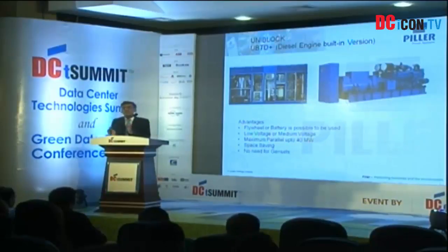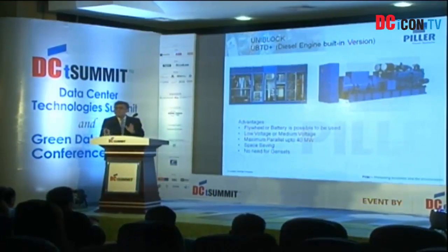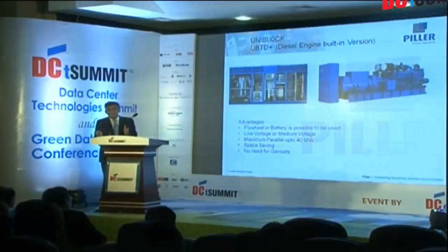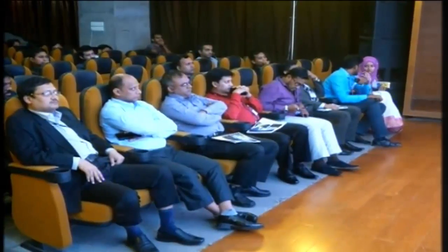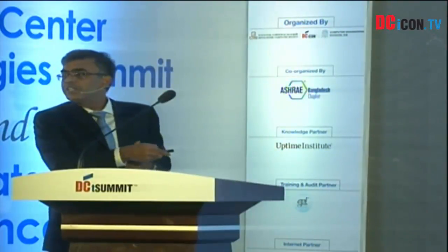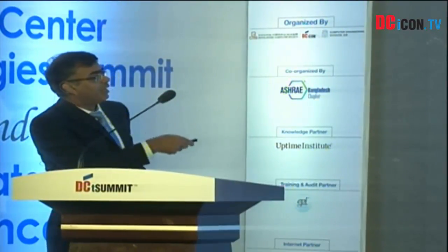Now, having introduced the rotary UPS concept to you, the only small variation here is the diesel rotary UPS, right? A rotary UPS can be used with a genset similar to a static UPS, whereas to save more space and to save the number of generators, we combine these two together and provide you a diesel rotary UPS system. This is a diesel rotary UPS system. The diesel engine, the uniblock which was vertical, is now horizontal, and coupled together with the diesel engine. Here is the flywheel and the switchgear. Everything else remains the same. The power capacity is the same, the voltage levels are the same, and the reliability of the machine is the same.